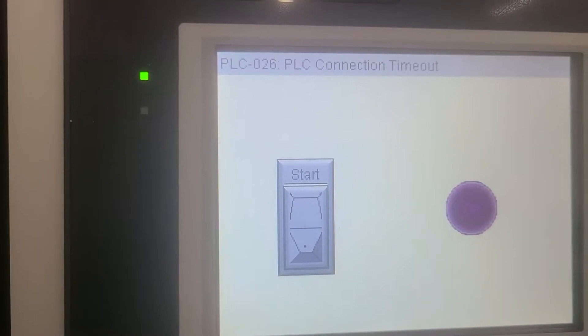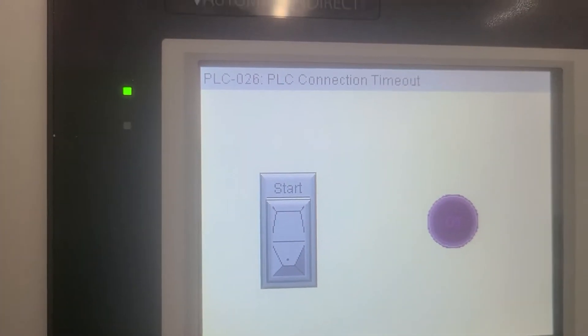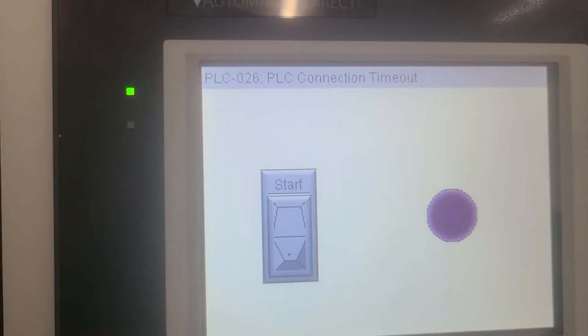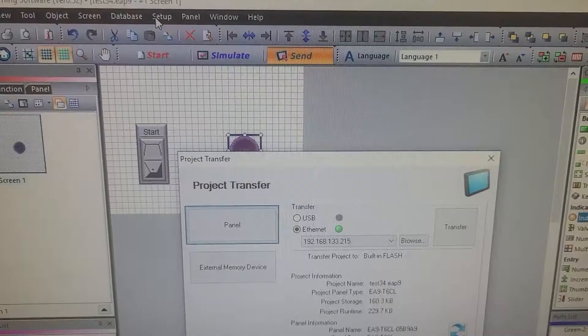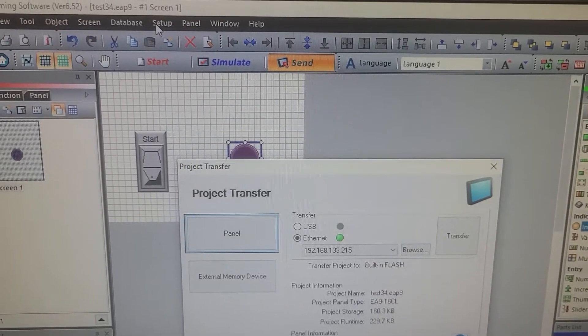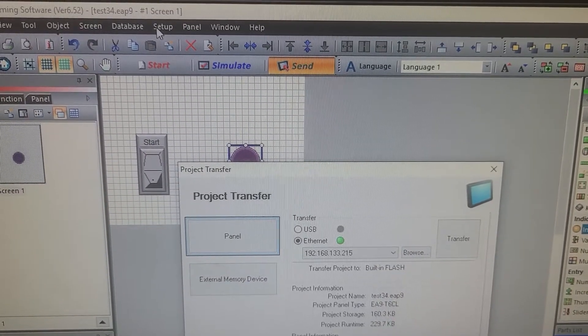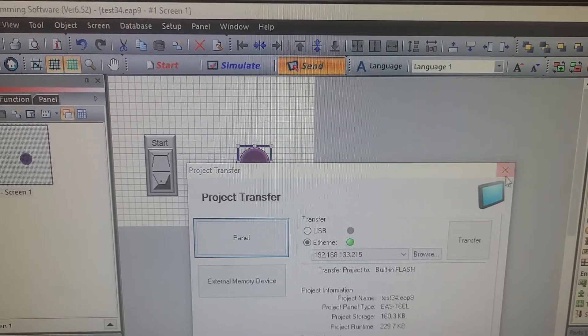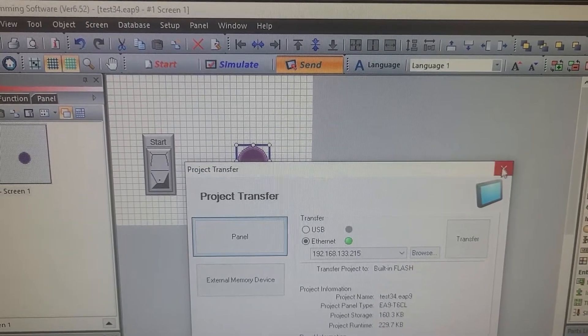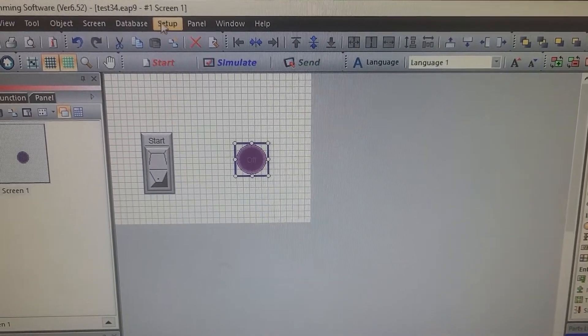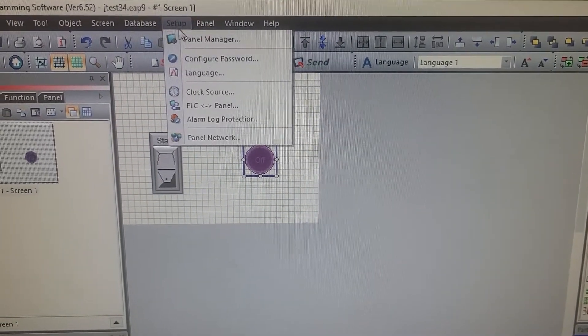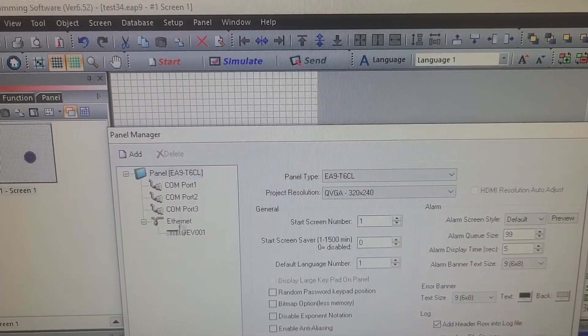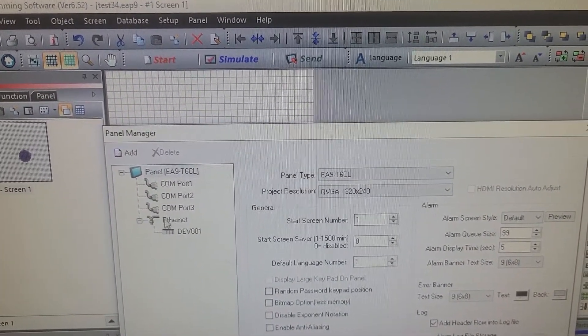If you're getting this PLC 026 connection timeout, let me show you what you probably missed. Probably what was missed is if you forgot to set up your IP connection or Ethernet connection for the C-More panel — for the PLC.